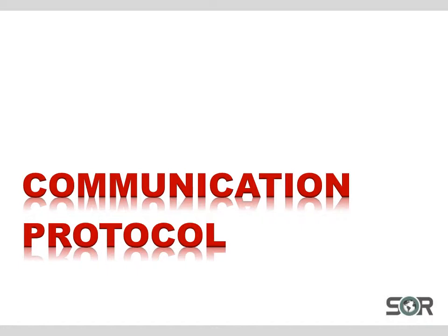Now let's talk a little bit about Modbus RTU. RTU is an acronym that stands for Remote Terminal Unit. Modbus is often used to connect a supervisory computer or master with an RTU in SCADA systems. SCADA stands for Supervisory Control and Data Acquisition. It is essentially a type of industrial control system. Modbus RTU is a master-slave type system that has one node, the master node, that issues commands to one of the slave nodes and then processes the responses from that slave. Slave nodes will not typically transmit data without a request from the master node and do not communicate with other slaves.